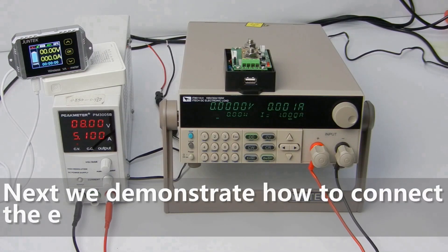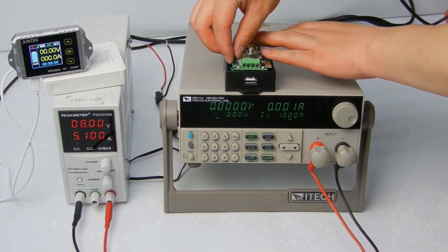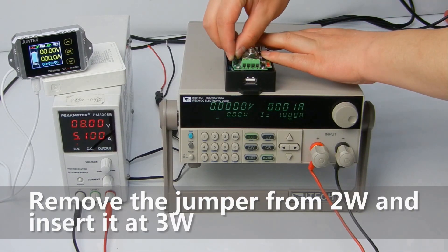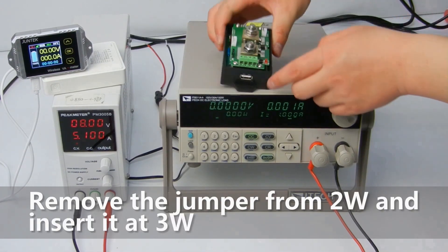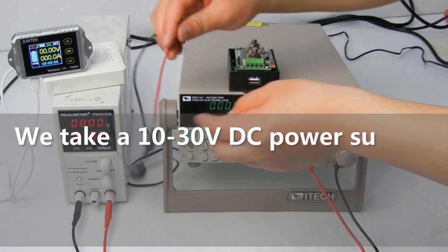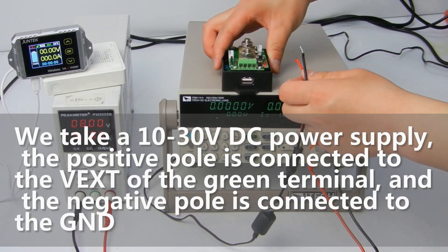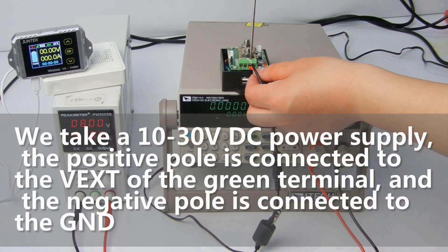Next we demonstrate how to connect the external power supply. Remove the jumper from position 2 and insert it at position 3. We take a 10 to 30 volts DC power supply. The positive pole is connected to the VEXT of the green terminal, and the negative pole is connected to the GND.